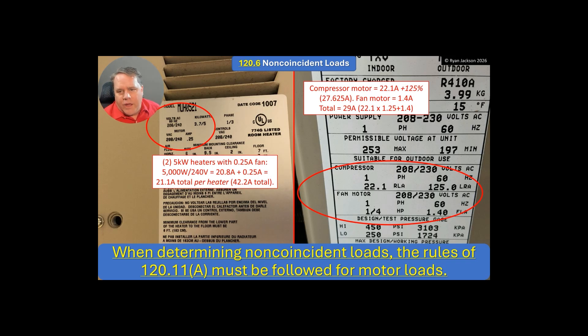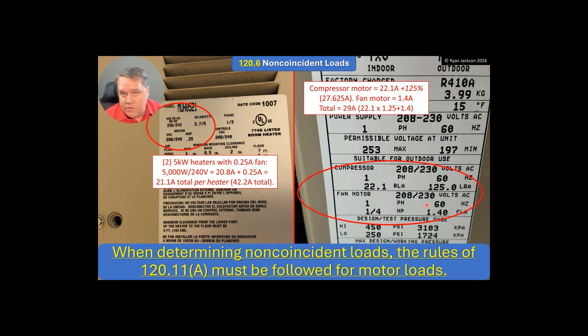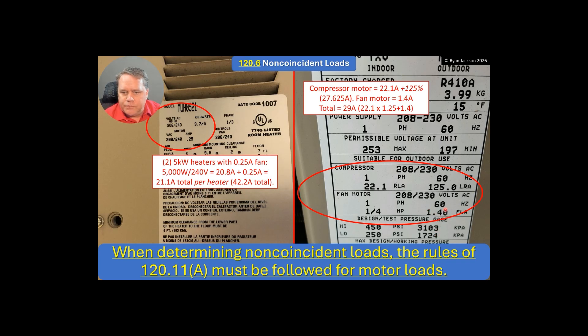Over here on the right, my compressor motor is 22.1 — that's the running load amps. I've also got a fan motor as part of that equipment, which is a quarter horsepower, so it pulls 1.4 amps. I'm going to take the larger of those two times 125%, which of course is going to be the compressor. So 22.1 × 125% is 27.6. On top of that, I'm going to add my 1.4, and that's going to be a total of 29 amps. So that's my air conditioning.